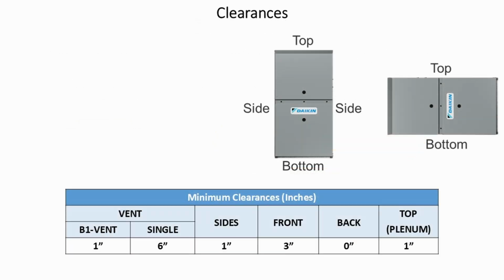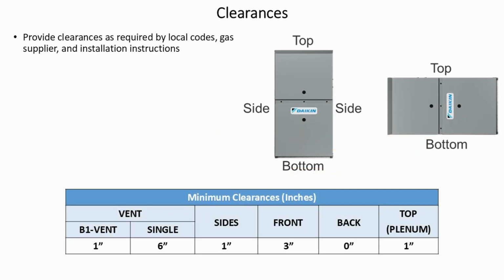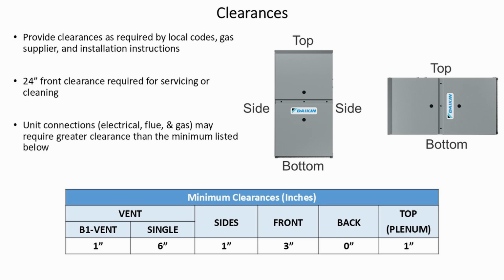Clearances. Provide clearances as required by local codes, gas supplier, and installation instructions. You need at least 24-inch front clearance for servicing and cleaning. Unit connections, electrical, flue, and gas piping, may require greater clearances than the minimum listed. See the chart below for minimum clearances in inches. Top clearance for a horizontal configuration is 1 inch.